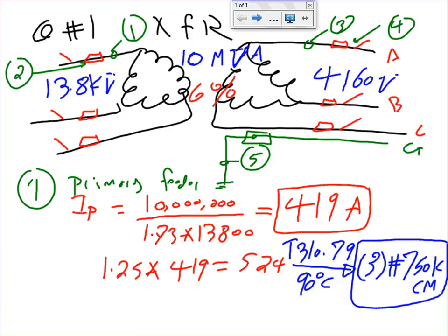Oh, okay. Yeah, they're underground ducts. They give you 20, I think 20 Celsius. Is that what they give? Yeah, 20 Celsius ground temperature, because you choose the table based on the ground temperature and the loading and a bunch of factors there. 750 kcm, one multi-conductor cable.